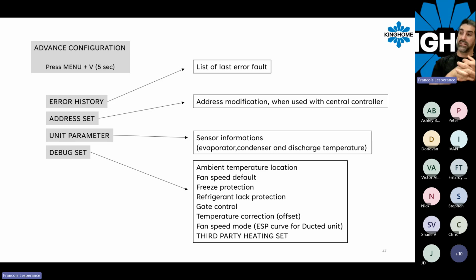And the fan speed mode, this is where, for a ducted unit, for example, you need to have this controller to adjust your ESP curve. So for a ductless ducted unit, whenever you select your fan speed, depending on the ductwork, you might need to adjust your ESP curve also. So you need to have this thermostat to do it.